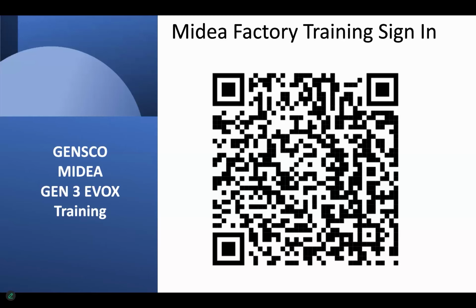Yes. So there's a board with the gas furnace coil that is very similar to the board in the air handler. It has a couple of extra terminal strips for connection to the 24-volt gas furnace. Other than that, it's very, very similar, and so we'll have very similar dip switch capabilities. And like we were talking about earlier with the S3 rotary dial, being able to set that rotary dial to an outdoor temperature to lock out the heat, we also have the same rotary dial on the coils that we can set for an outdoor changeover for the compressor.